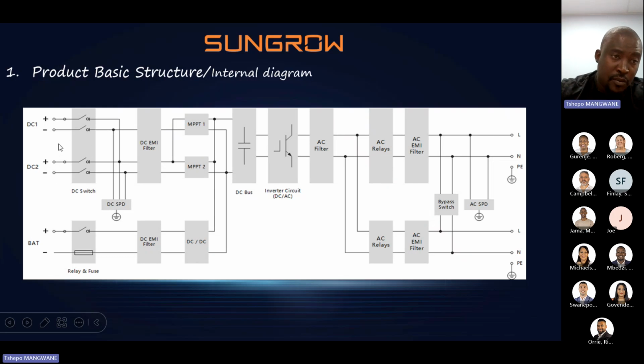So power being transmitted from our MPPTs will be transmitted to the main DC EMI filter board. From the EMI filter board, it will go into our boosters on MPPT1 and MPPT2. From MPPT1 and MPPT2, it will be transmitted to the main common DC bar. This tells us that PV can charge the battery directly, because they meet up on the common DC bar. All right. So this is our positive pole and negative pole of the battery. It has a built-in fuse as well. It comes with the switch gear on the side of the battery. So power coming from the battery side will be transmitted to the DC EMI filter board.